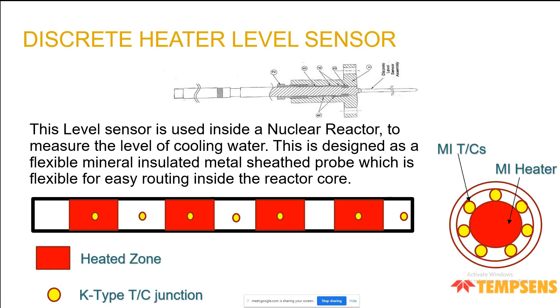In this design, we use a heater with distributed heating, so there is heating only in the red zones. Mineral insulated thermocouples are placed alongside this heater and then compacted within an outer metal tube, at different lengths. The electronics then provide the level to which the liquid has been filled.